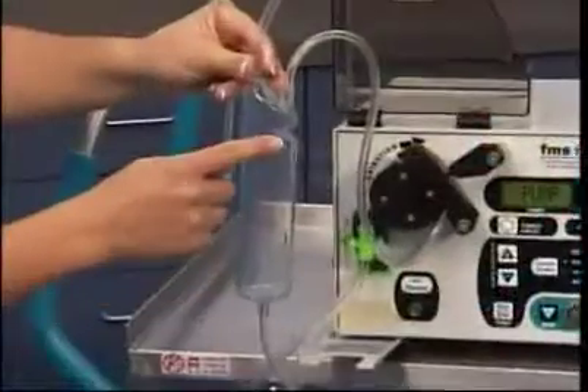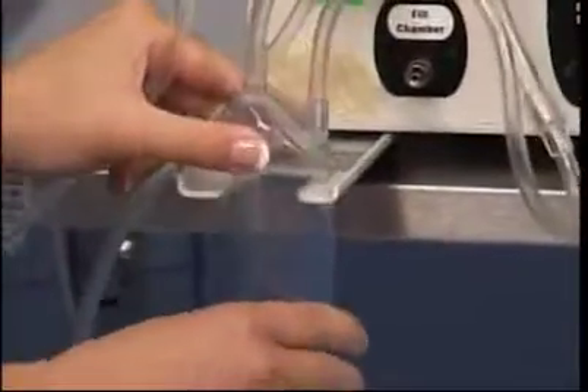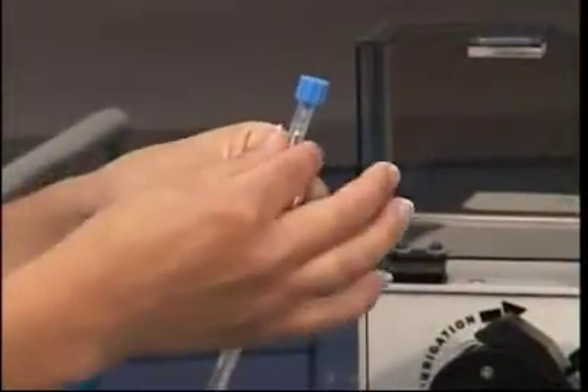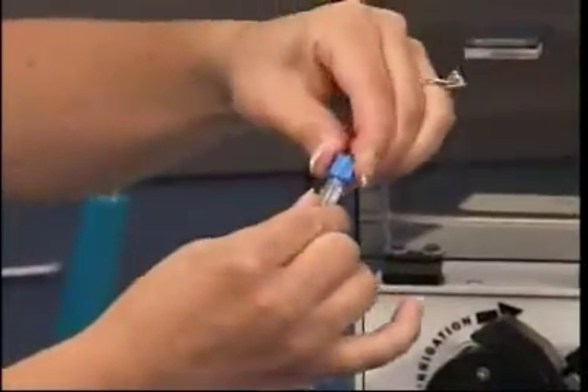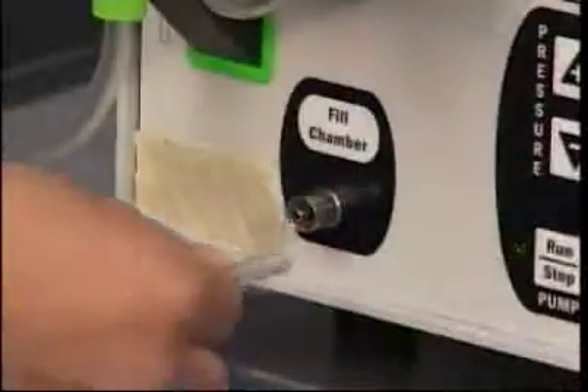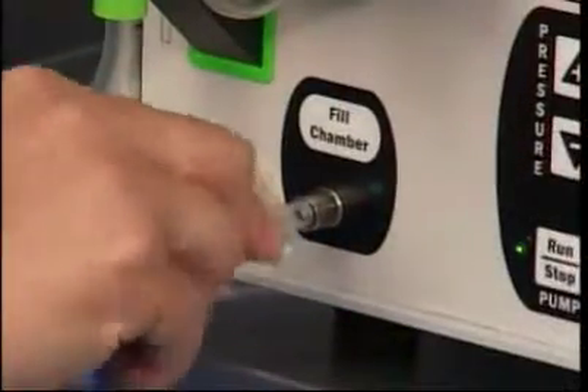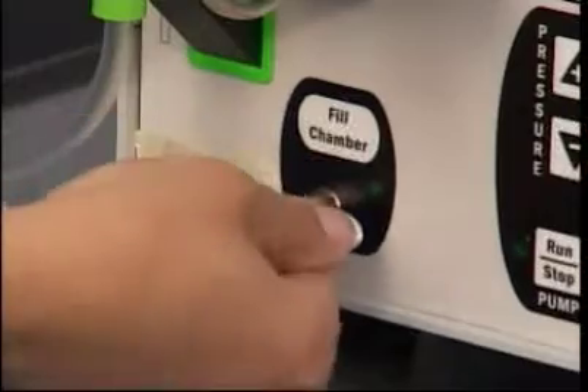Place the pressure chamber into the holder. There is a groove near one end of the chamber. Slide it into the holder and make sure it remains vertical during the procedure. Unscrew the cap to the transducer. Next, screw the transducer into the plug below the fill chamber button. Turn it slightly left before turning clockwise. Make sure it's tightly screwed in.